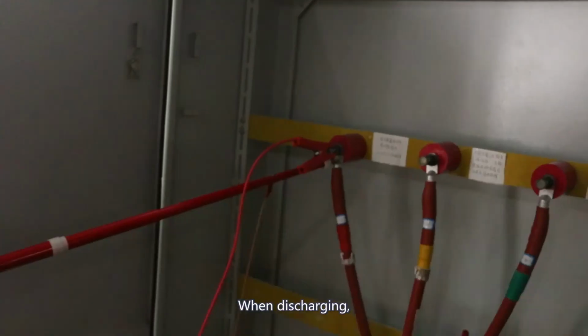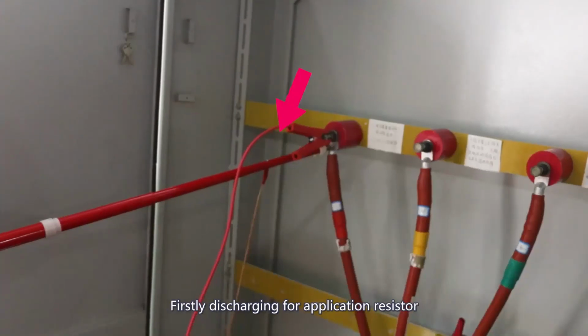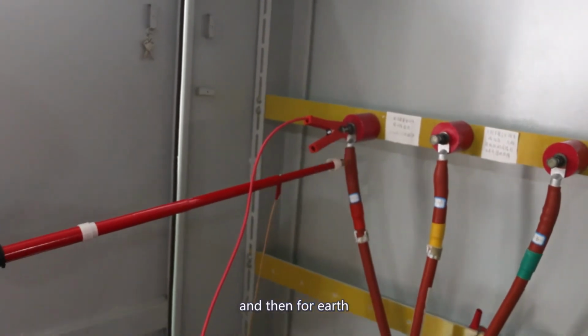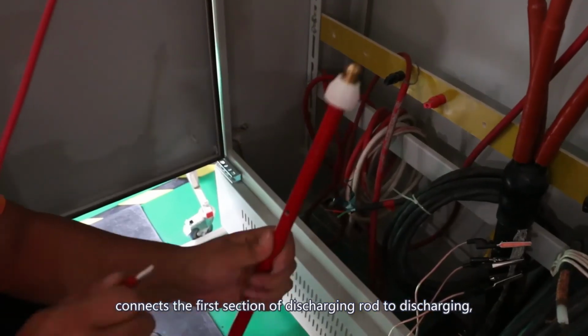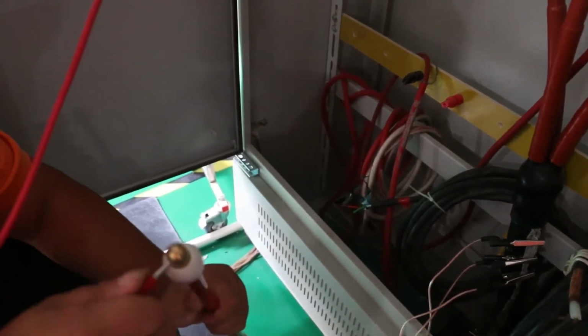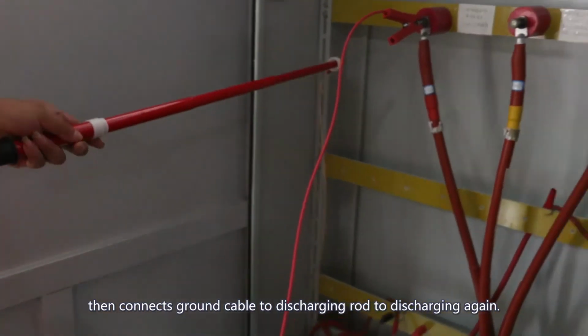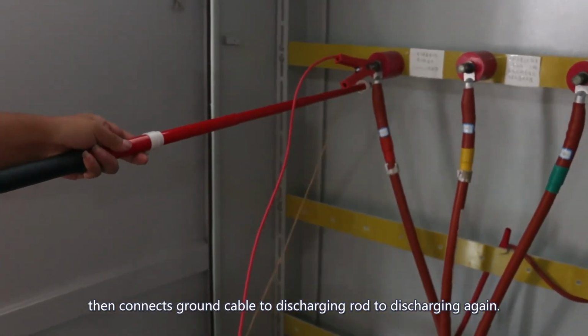Turn off the machine, disconnect plug, collect leads. When discharging, firstly discharging for application resistor and then for earth, connects the first section of discharging rod to discharging, then connects ground cable to discharging rod to discharging again.